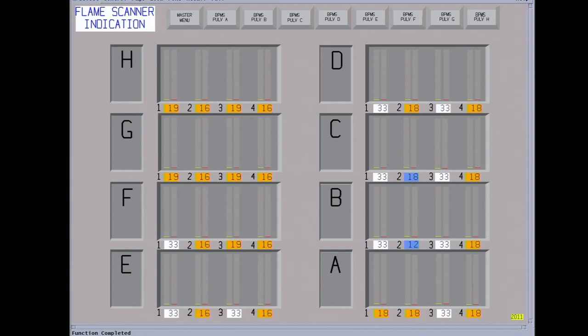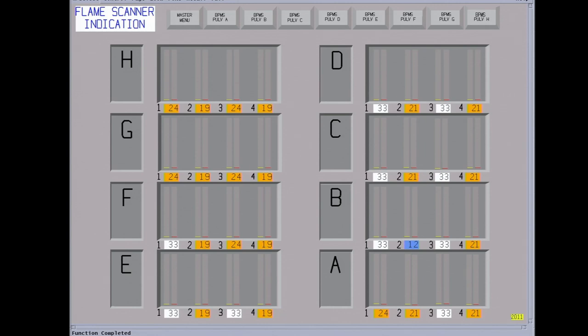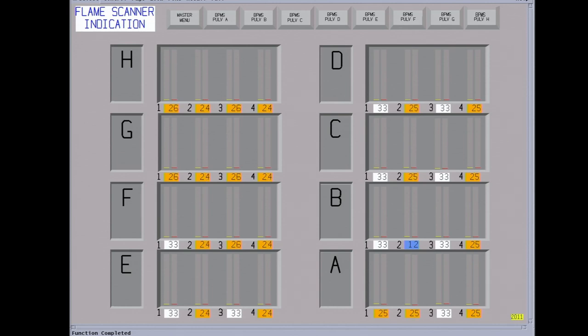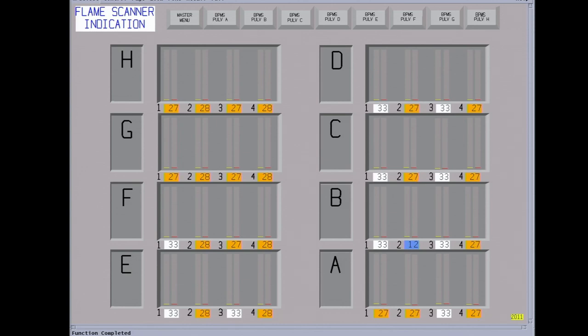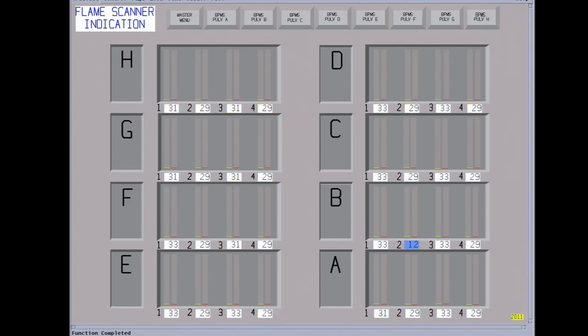Okay, you can see all the dampers are moving. They'll have to go, the blue is cool down. That's minimum air flow just to keep the burner cool. The light off is white. That's adequate air flow to ensure good combustion. Before we put fires in this, we'll have to start the precipitator and the DSI, which is dry sorbent injection to remove any sulfur. And we'll have to start all the mercury removal emissions.